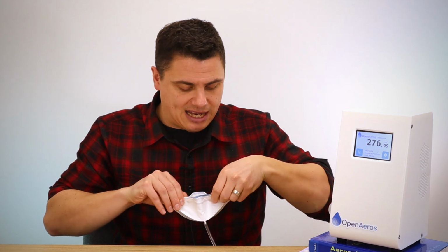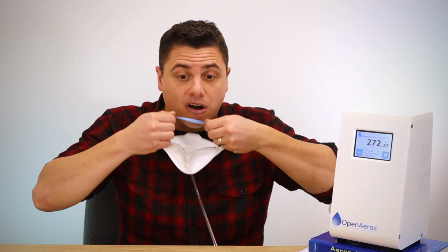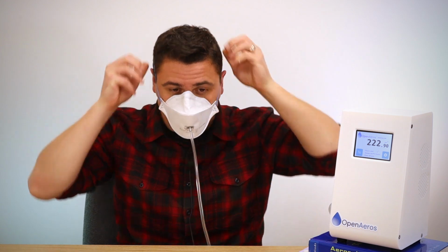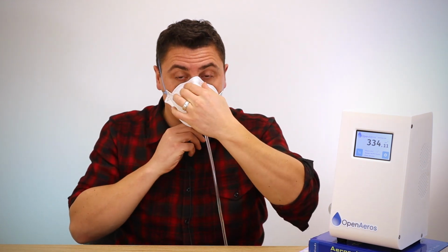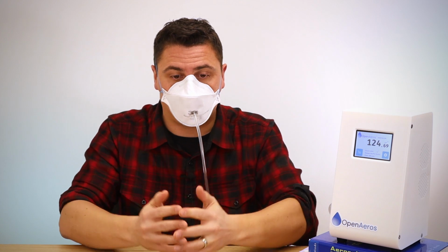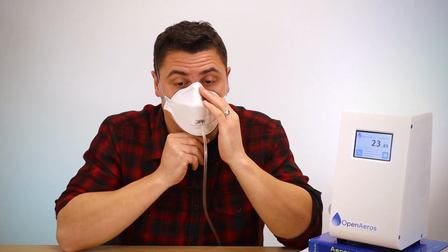What they discovered is that by taking advantage of all these tiny particles that are already present in the space, they could measure how well the respirator fitted by measuring the reduction of particles that could be measured inside the mask via this mask port. Taking advantage of all these ultrafines, they could actually measure how well a mask was fitting on a person's face and how effective it was. And as you can see on the display here, you can see the reduction of the counts, and they should be dropping down to about 3 to 5 particles per cc, which represents roughly a 99% removal rate by this mask.